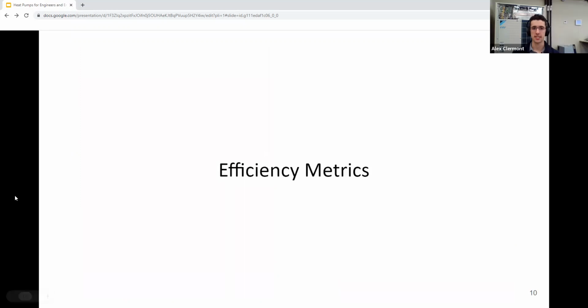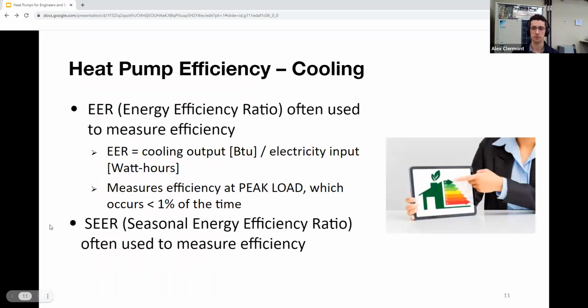Now we'll get into the most common types of efficiency metrics for air source heat pumps and water source heat pumps as well. In cooling, there's 3 main different kinds. There's EER, SEER, and IEER. First of all, we'll talk about EER, which is the energy efficiency ratio, which is the efficiency of the system at peak load. Now, Jason's going to go into this in a little bit, but peak load is rarely seen.